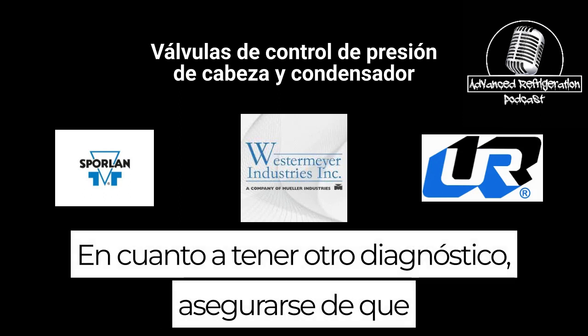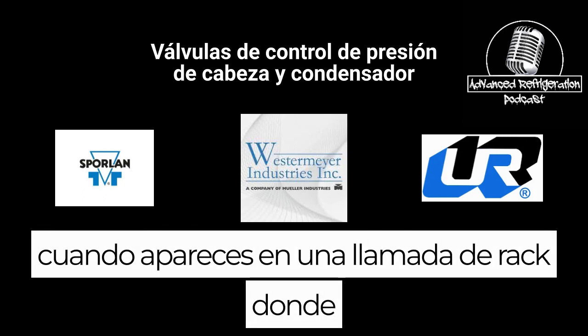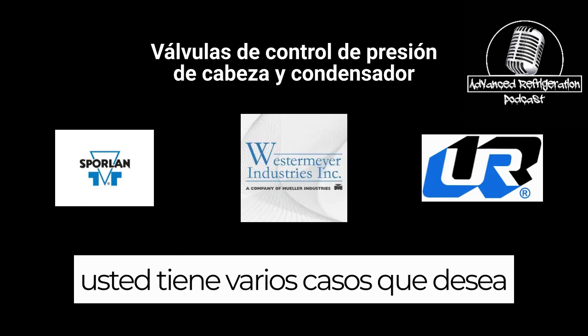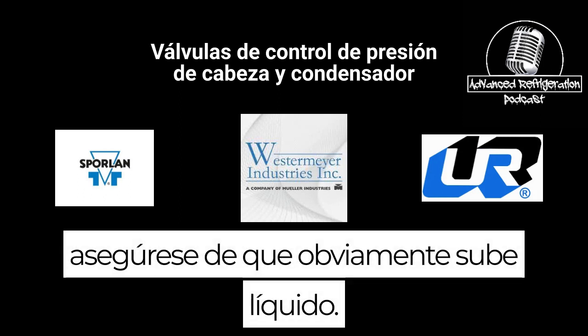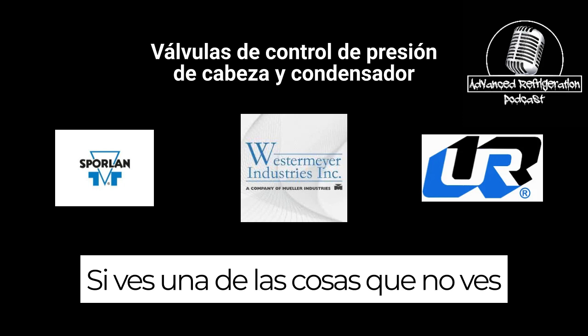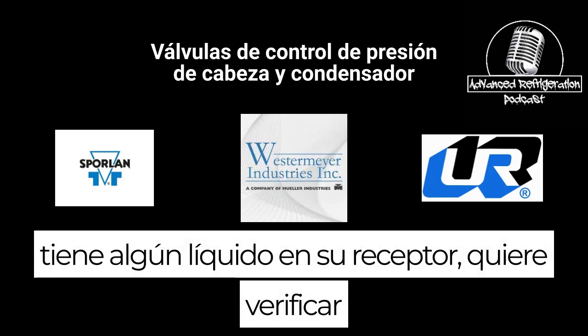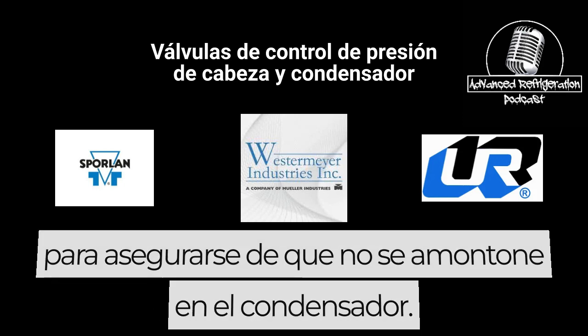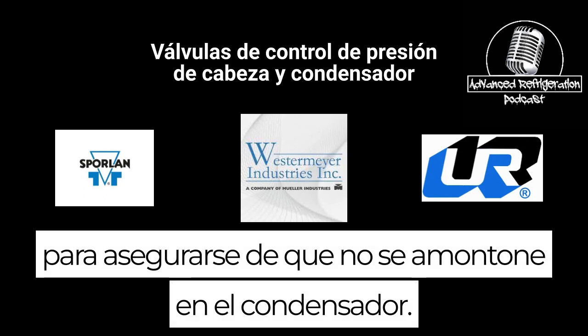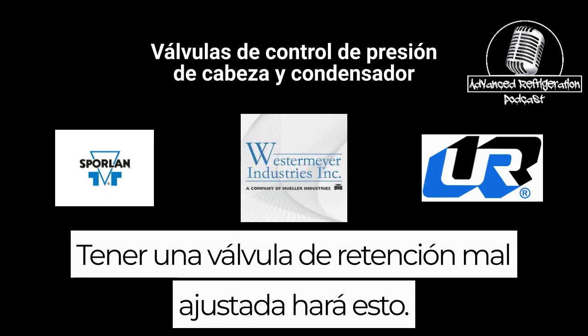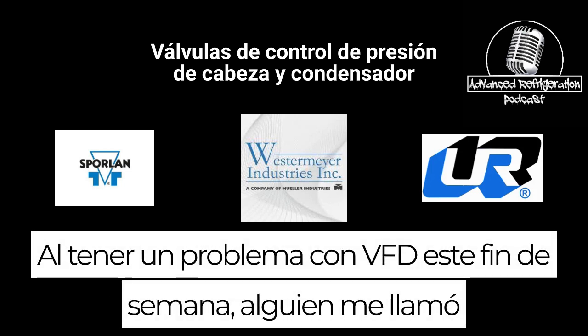As far as another diagnostic, when you show up on a rack call where you have multiple cases, you obviously want to make sure you have enough liquid. If you see that you don't have any liquid in your receiver, you want to check to make sure it's not stacking in the condenser. An ill-adjusted holdback valve will do this. Having a VFD issue will do it too.